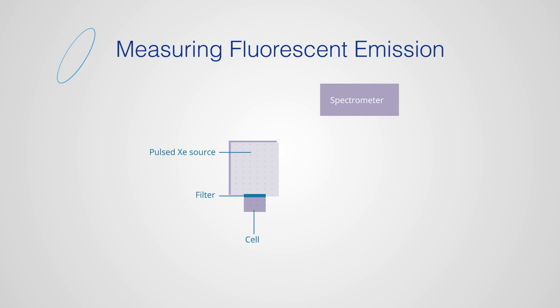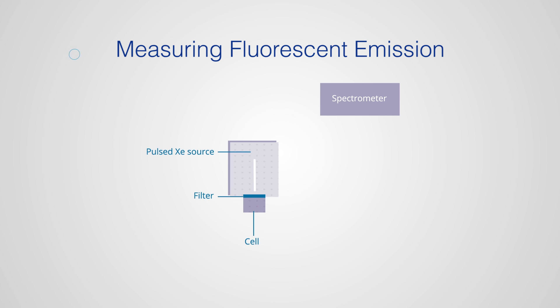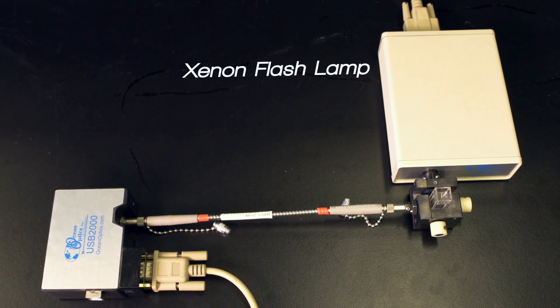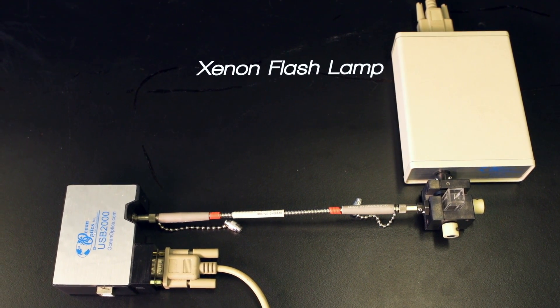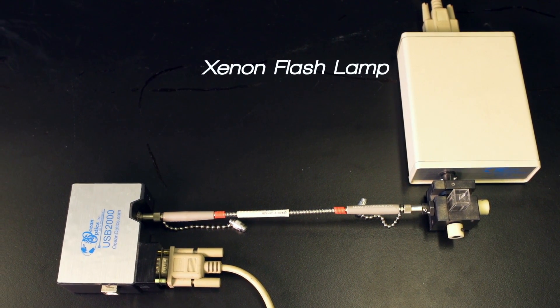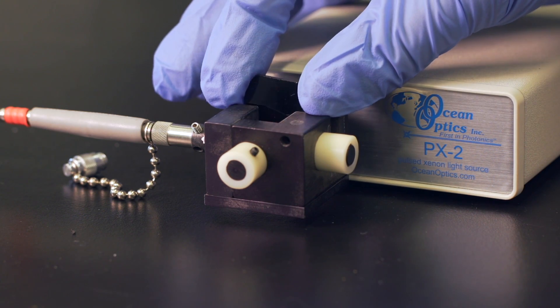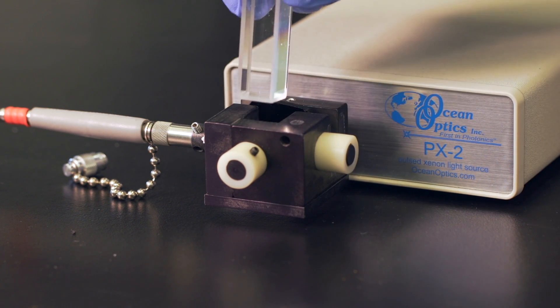When measuring fluorescence emission, a different instrumental setup is used. In this configuration, the emitted light is collected and measured perpendicular to its original direction, to reduce the amount of scattered light being detected. The light source is a xenon flash lamp that pulses on and off, and a signal is only collected when the lamp is on. The light beam passes through a bandpass filter and into the cell.